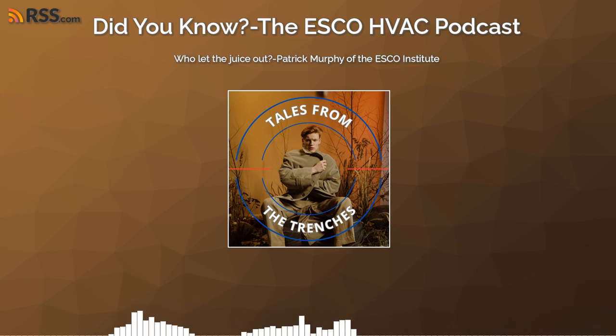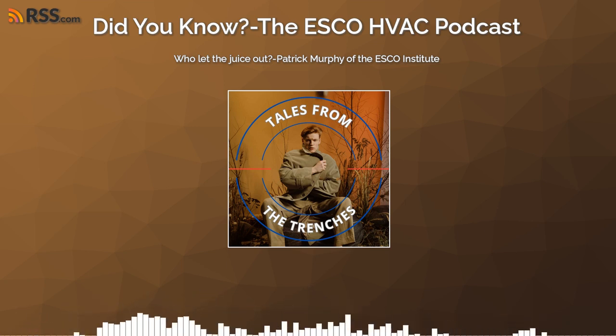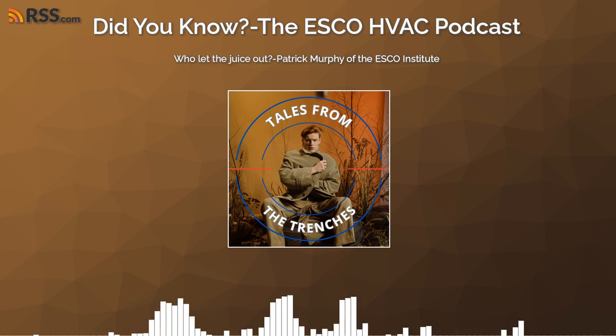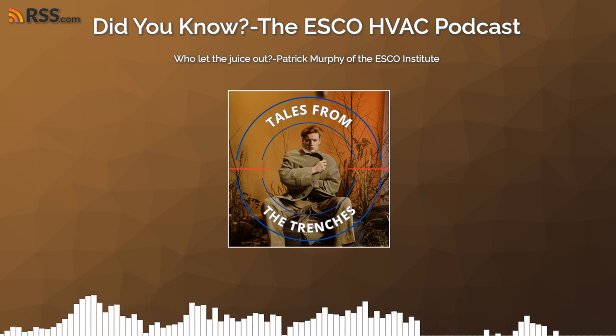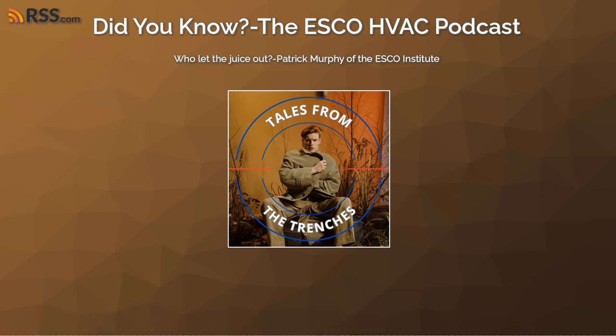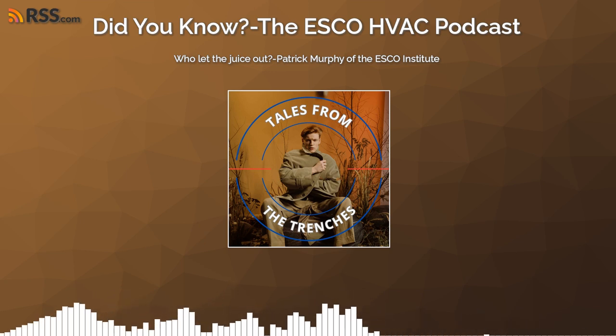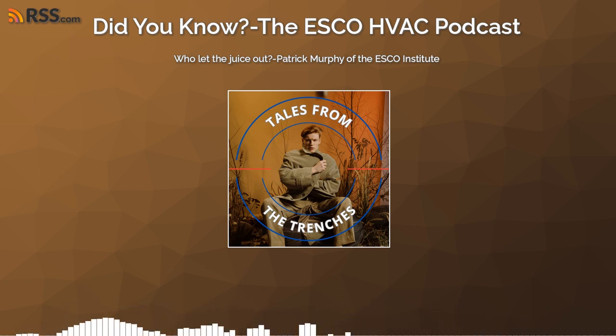You open the unit up and the condenser fan motor is very hot, but you look at the shaft and it has this lovely roping around it. You trace it back and find out it's a vine that grew through a gap into the condenser area, wrapped itself around the shaft, the shaft spun around, and seized the motor. Once you cut everything loose and the motor cooled down, everything was fine. Which brings up another point — how often do we have to expedite cooling a condenser fan motor? One of the tricks of the trade is to grab a garden hose and help cool down a condenser fan motor or a compressor that is overheated.